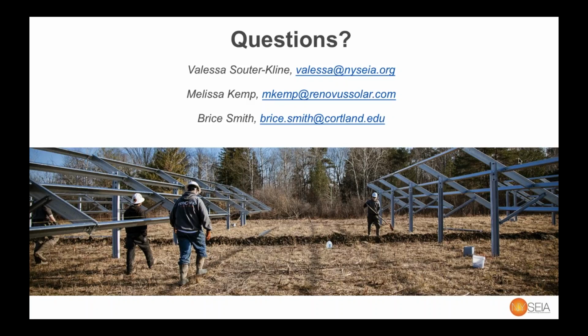It is possible to connect to these types of systems in other jurisdictions that have these kinds of high penetration of solar. For instance, in California, in their version of Screen A, if you are connecting to a networked system, they do allow that explicitly under their screening analysis for spot networks where you are interconnecting less than either 5% of the spot network's maximum load or 50 kilowatts. And they take those two limits. So those smaller systems are allowed under the screens, but with the explicit requirement that there be no possibility of backfeed out of that spot network. So again, there are possibilities.